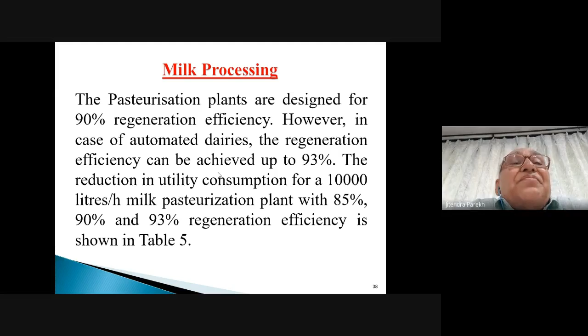Now I have shown on the left side the regeneration efficiency in the pasteurization plant: 85%, 90%, 93%. When you increase the efficiency, the running cost, as you can see on the right hand side, has gone down substantially. So it is better to have more regeneration efficiency, by putting in more plates or designing accordingly. This is mainly happening with automatic plants. But if you can get 90% regeneration efficiency, there is a lot of running cost saving.